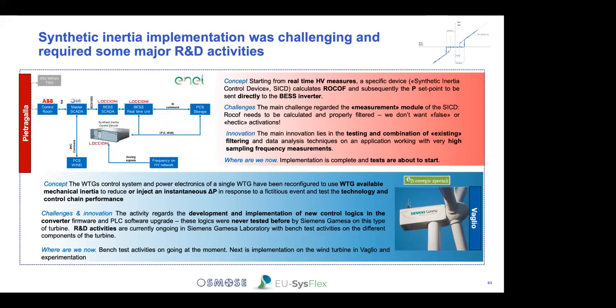In Pietragalla, there is a system called SICD, Synthetic Inertia Control Device, which measures the rate of change of frequency (ROCOF). The measurement is filtered, and then used to compute a power point, which is sent directly to the BESS system inverter. The main challenge here was the measurement module of the SICD, starting from the very high sampling frequency measurements. Now the tests are basically about to start.